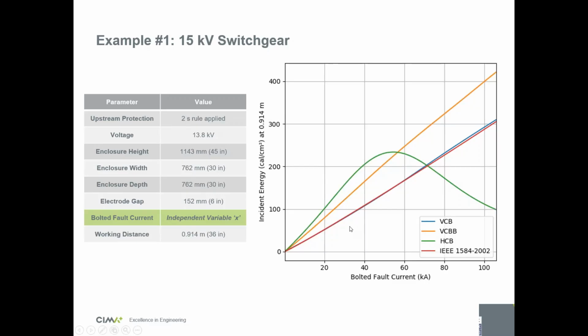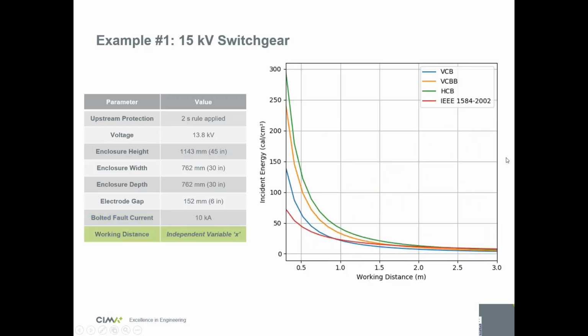So this is a bit of an interesting result here. Normally when you do an arc flash study, you try to find the worst-case incident energy by varying your scenarios. So you see, for example, low fault current, medium fault current, high fault current, generator, and then you put a few points and try to find your worst. But in this case, you can see the actual worst is exactly at this value. And then your working distance follows an inverse square law, so the more you move away from the source of the arc, the more the energy drops.